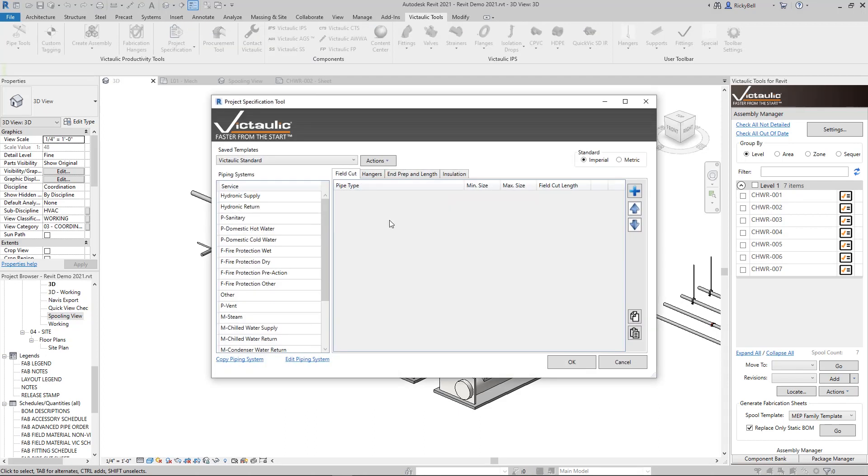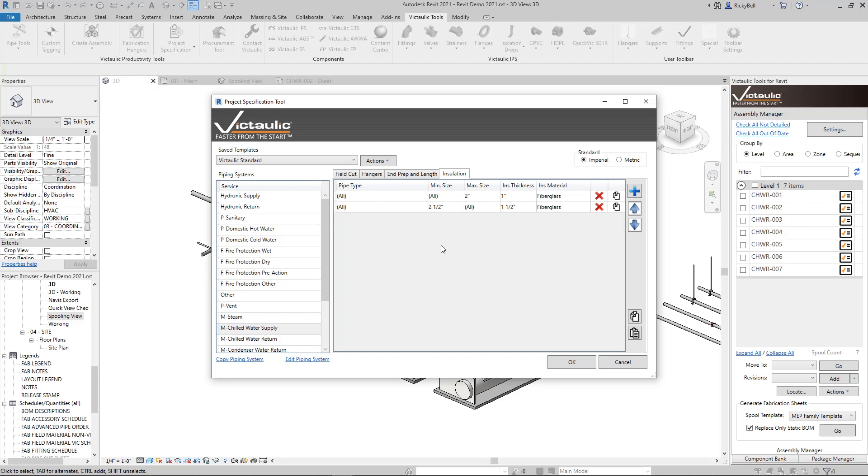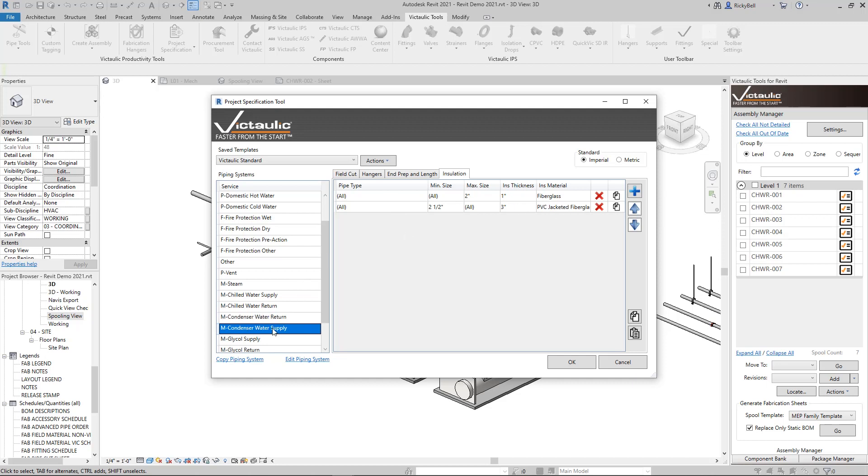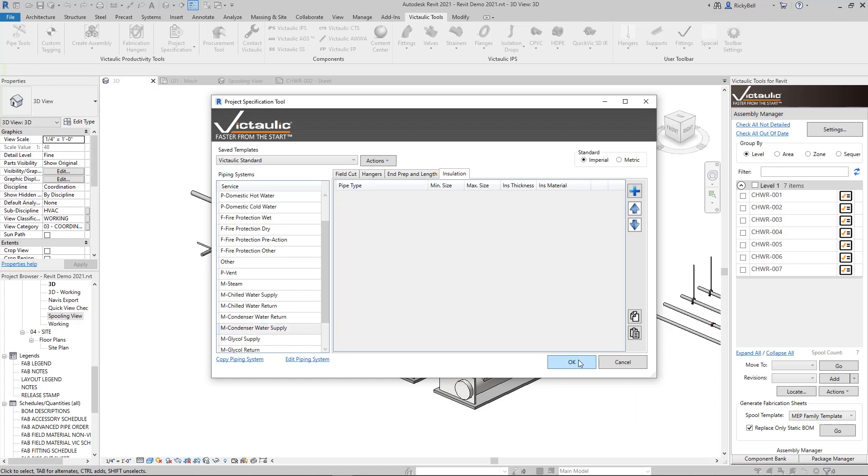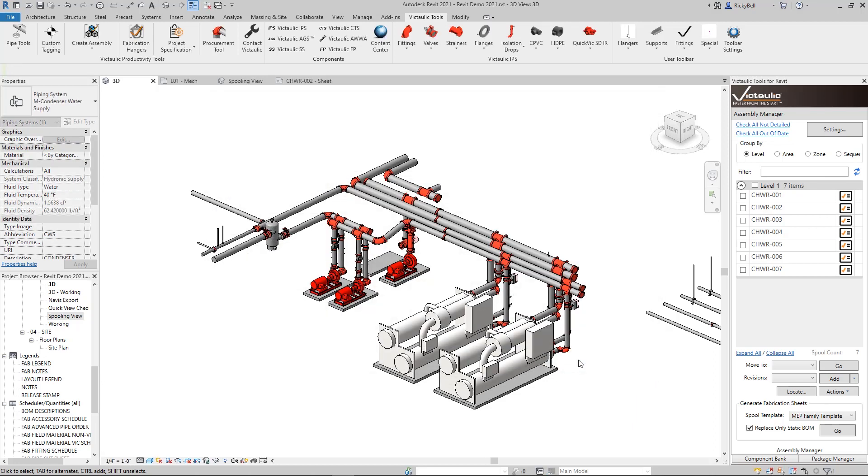Let's take a look at the project spec and chilled water supply for insulation. Right now it just says everything over two and a half inch is going to get an inch and a half of fiberglass, chilled water return, same. And this is pretty typical. Now for the condenser water return, let's do something a little larger. Let's do like three inches of insulation. And maybe for water supply there's no insulation, so I can clear these out.